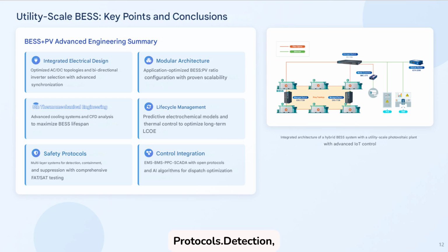Safety protocols: detection, alarm, suppression, and isolation systems for thermal and electrical faults. Full FAT/SAT test validations with regulatory criteria and network testing: LVRT, black start, ride through. Post-mortem diagnostics with CT, chromatography, and BMS log analysis. Safety is not reactive. It must be designed, tested, and audited from the engineering phase.